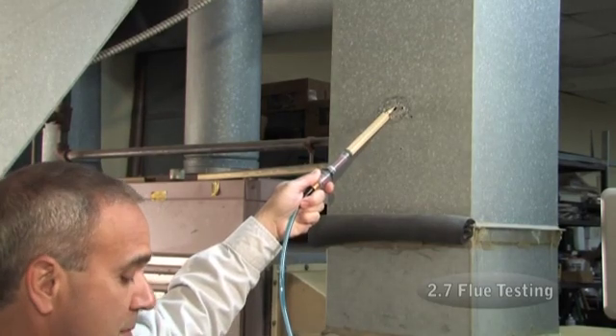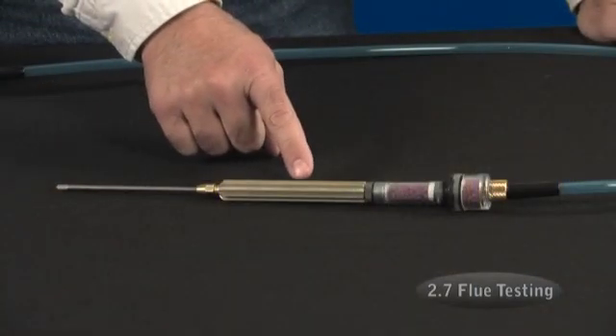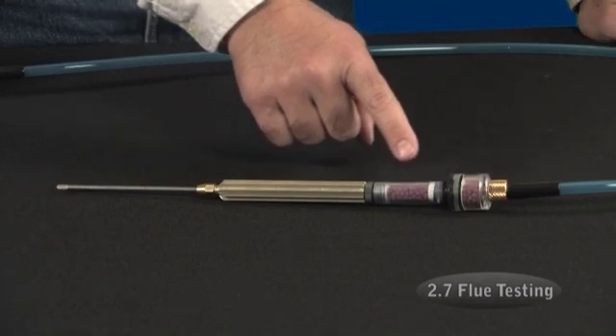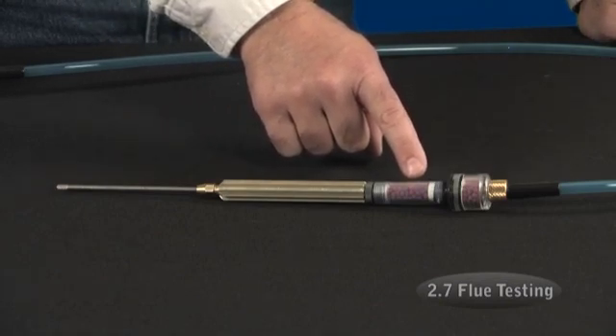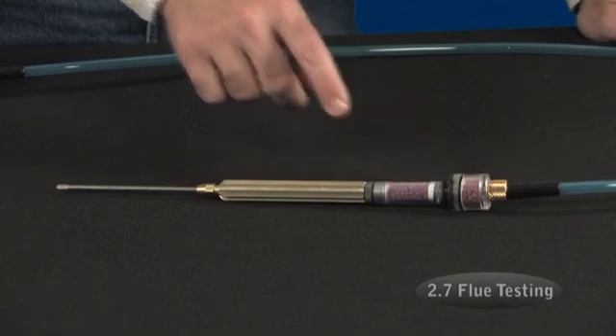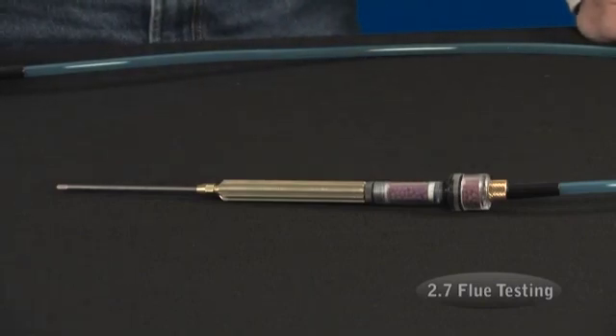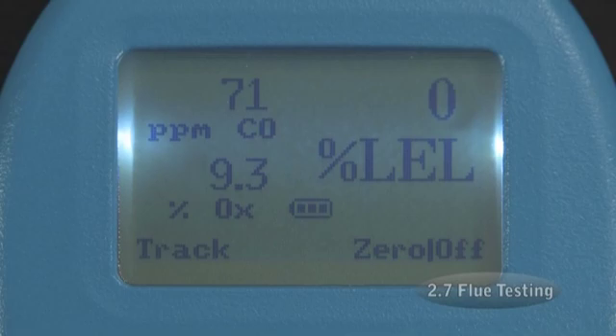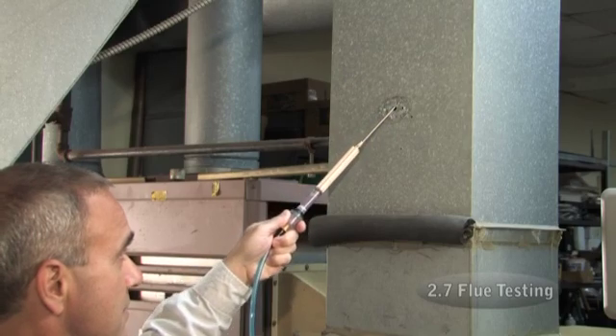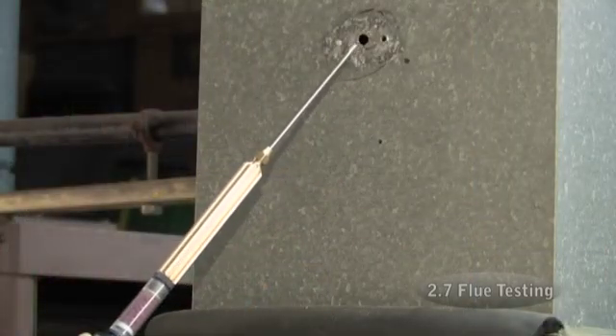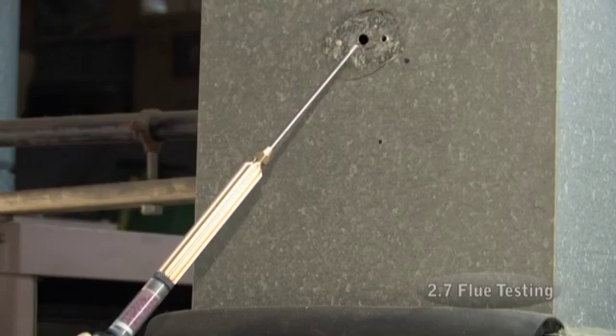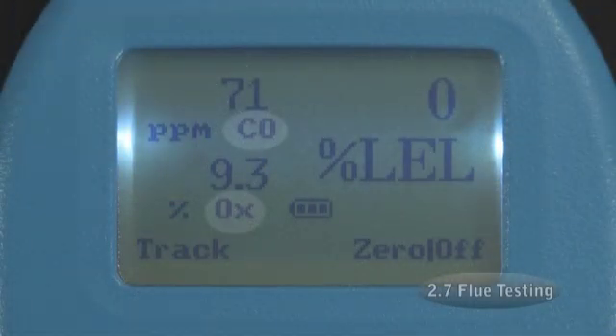As you know, flue gas is hot, moist, and contaminated. The probe will cool the sample, and the purple beads will remove substances that interfere with CO detection. The flue gas probe is rated for about 1.5 minutes of operation, sufficient for the detector to give you a full carbon monoxide reading. After you remove the tip from the flue, let the probe cool before you handle it to avoid burning yourself. If your unit is equipped with both a CO and an oxygen scale, you can perform what is called an air-free CO reading.